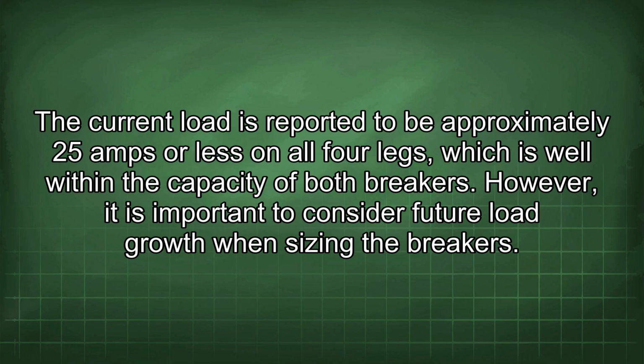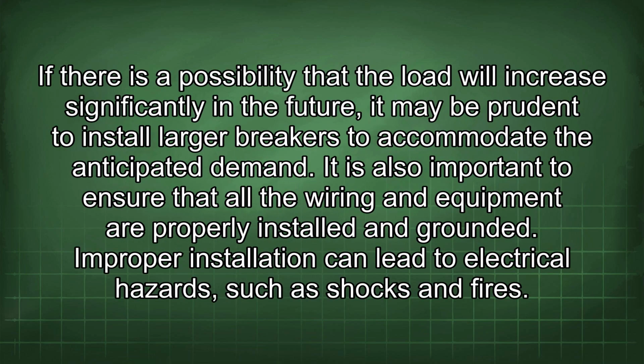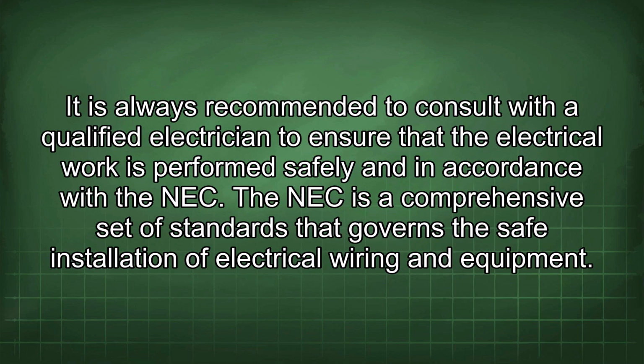However, it is important to consider future load growth when sizing the breakers. If there is a possibility that the load will increase significantly in the future, it may be prudent to install larger breakers to accommodate the anticipated demand. It is also important to ensure that all the wiring and equipment are properly installed and grounded. Improper installation can lead to electrical hazards such as shocks and fires. It is always recommended to consult with a qualified electrician to ensure that the electrical work is performed safely and in accordance with the NEC.